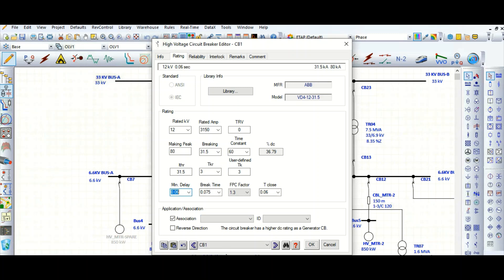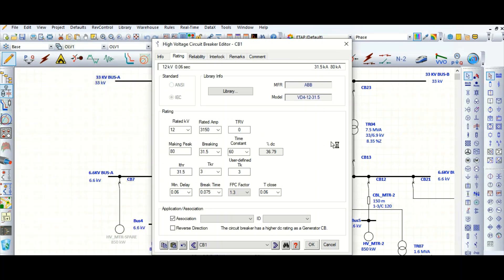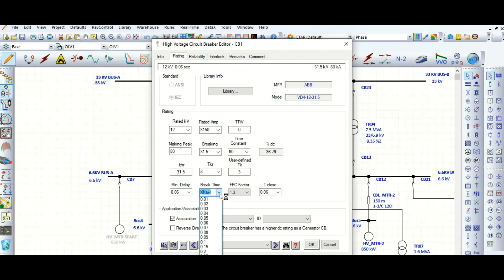Let's explain why this happens. During fault conditions, the first half cycle shows the peak asymmetrical value — the dotted line in between is the DC component. Because of this, the first few cycles, particularly the first half cycle, have a large asymmetrical peak value. The DC component decays over time, so when you provide more delay before the circuit breaker operates, the percentage DC component is lower. Here is the break time — you can select from the drop-down list at what time you want to break the circuit breaker.